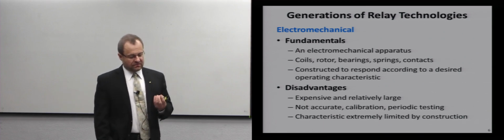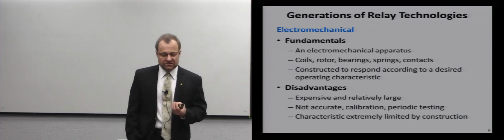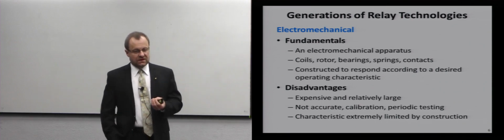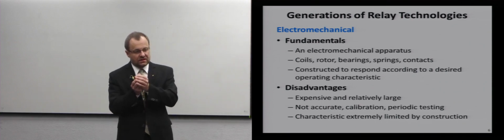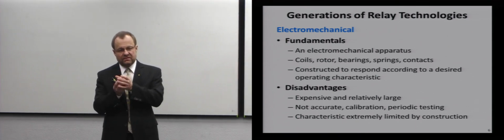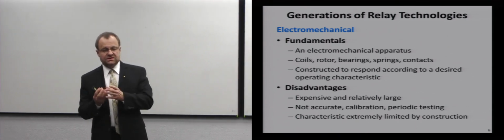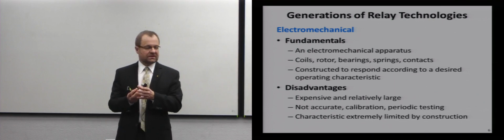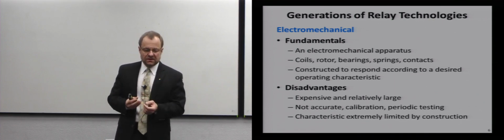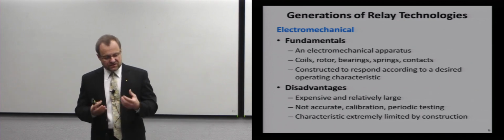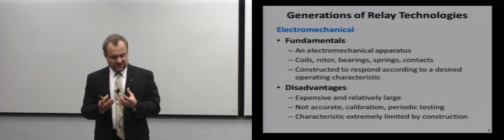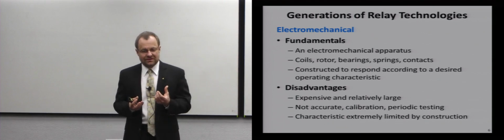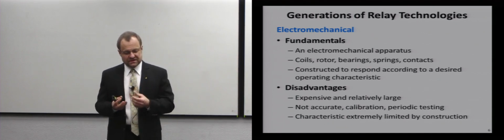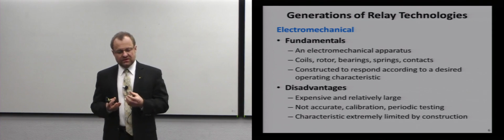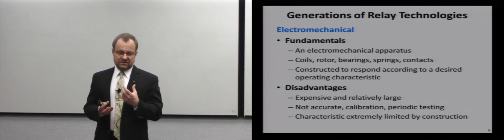So what are the fundamentals? Fundamentals are that you have an electromechanical apparatus. You have a little micro machine with iron core, with bearings, with the coil that follows a certain principle, meaning that you give it a current above the pickup threshold and the contact will close. So this thing will have bearings, springs, contacts. It's a Swiss watch made for protective purposes. It's constructed to respond according to the desired operating characteristic.